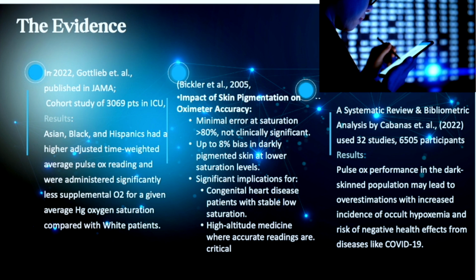All three pulse oxes showed overestimation in the dark-skinned individuals that increased linearly as their SpO2 levels decreased. This was an error caused by dark skin pigmentation in three different oximeters and was generally less extreme when the oxygen saturation levels were above 80% and likely has little clinical impact.